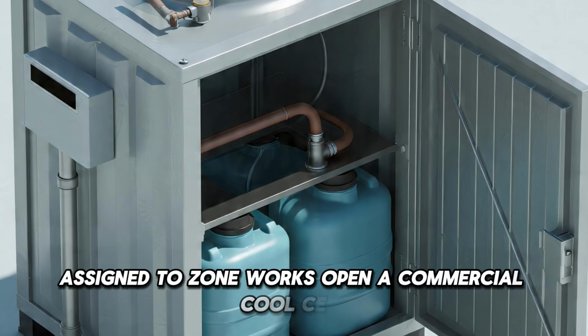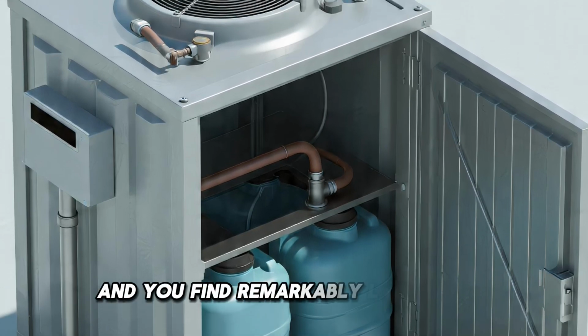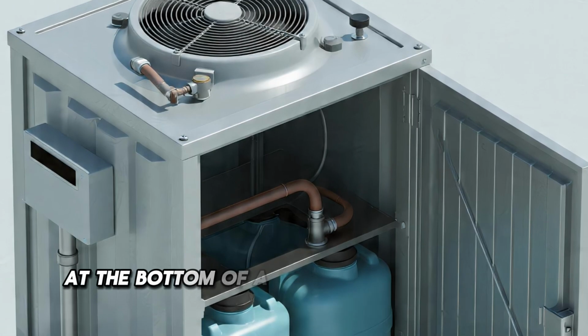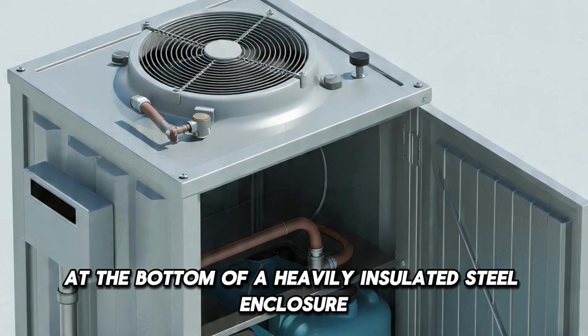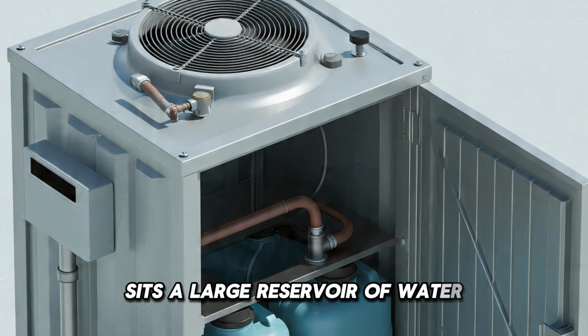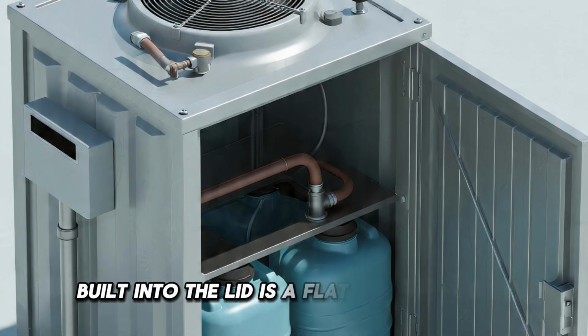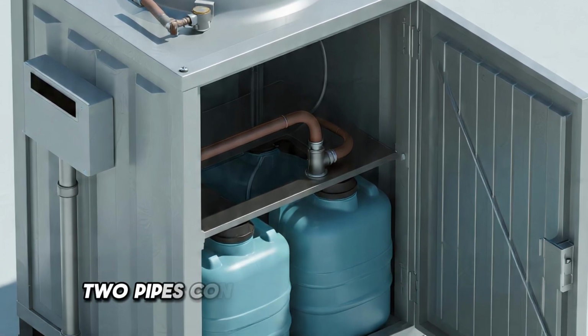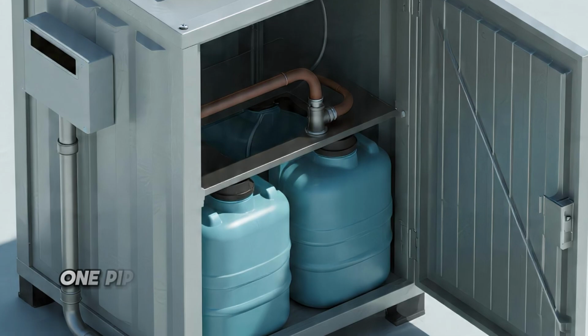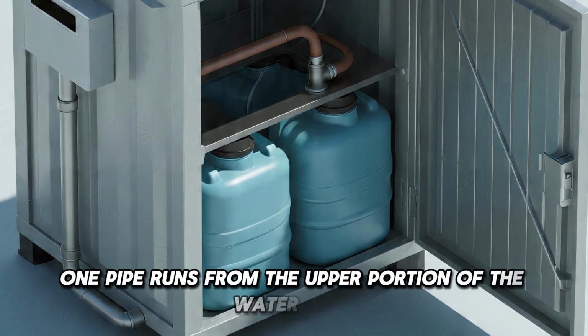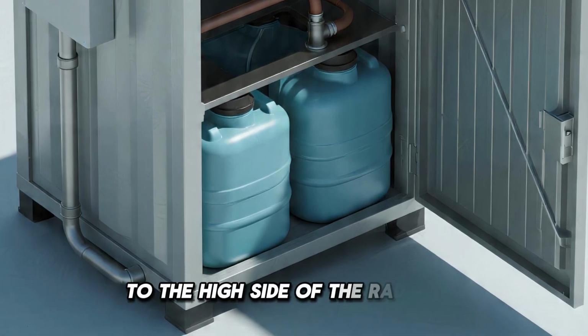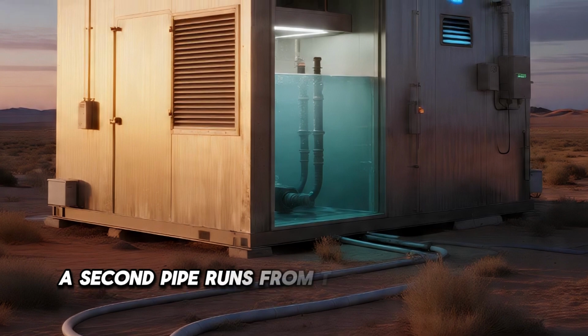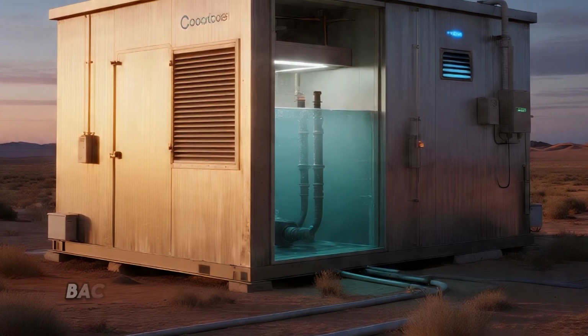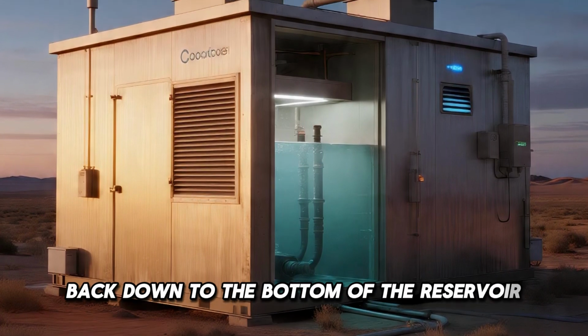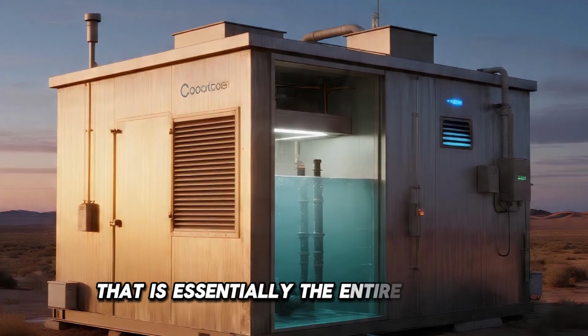Open a commercial cool cell, and you find remarkably little inside. At the bottom of a heavily insulated steel enclosure sits a large reservoir of water. Built into the lid is a flat-plate radiator. Two pipes connect the two components: one runs from the upper portion of the water tank to the high side of the radiator, and a second runs from the low side of the radiator back down to the bottom of the reservoir. That is essentially the entire machine.